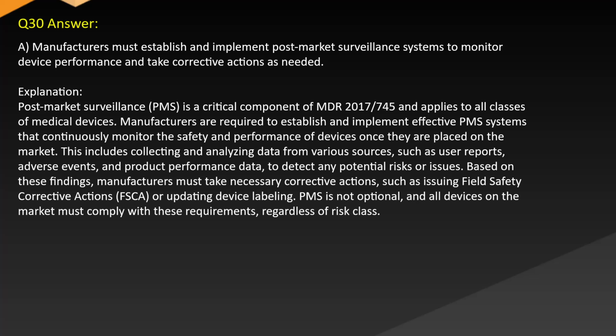This includes collecting and analyzing data from various sources, such as user reports, adverse events, and product performance data, to detect any potential risks or issues. Based on these findings, manufacturers must take necessary corrective actions, such as issuing field safety corrective actions, FSCA, or updating device labeling. PMS is not optional, and all devices on the market must comply with these requirements, regardless of risk class.